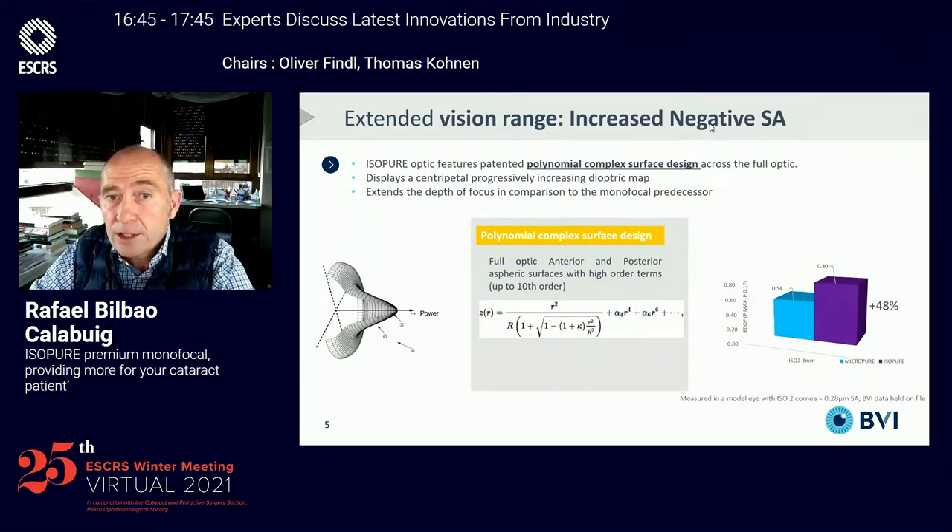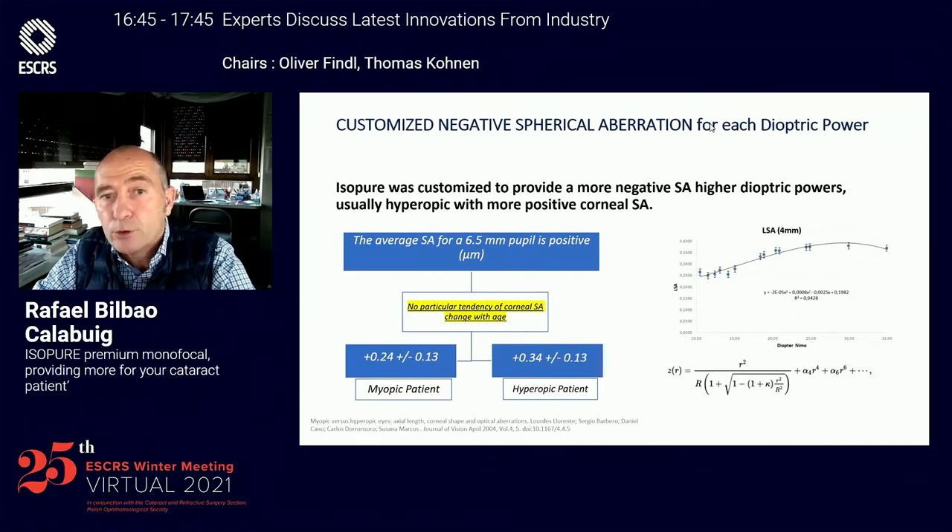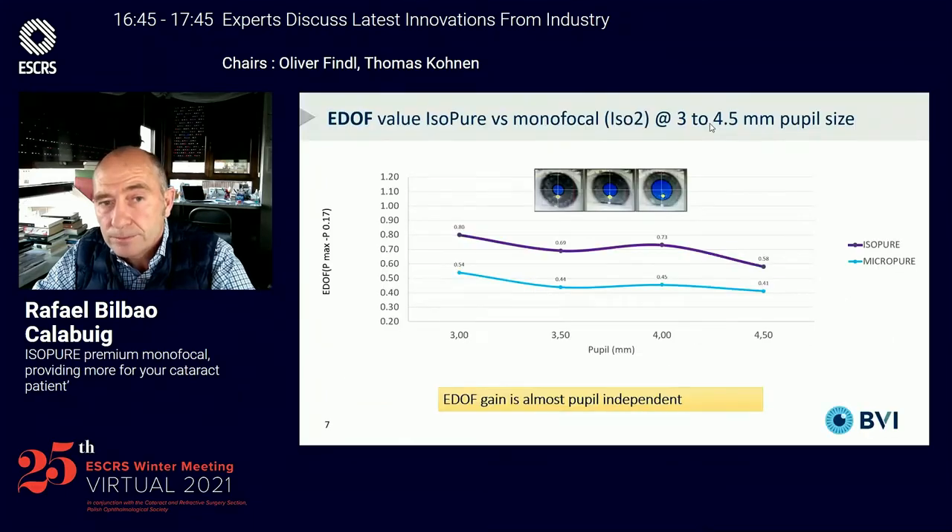The ISOPURE lens works with a polynomial complex surface design across both surfaces of the optic that displays a centripetal, progressively increasing dioptric map that extends the depth of focus in comparison to the monofocal predecessor by up to 48%. The ISOPURE was customized to provide a more negative spherical aberration in higher dioptric powers, and has been shown to be almost pupil-independent compared to the monofocal predecessor.